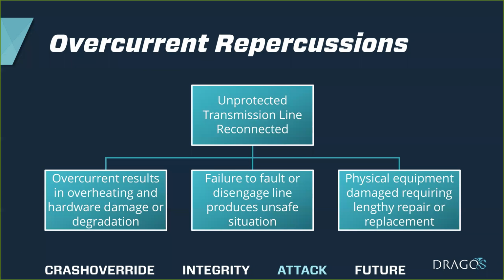And many of these conditions can combine to produce a scenario where, instead of it just being a matter of reclosing a lot of open breakers, you now have to actually repair or most likely physically replace damaged gear, which takes an outage that was originally a couple of hours into something that could last a couple of weeks or maybe even a couple of months, depending upon what equipment is damaged and to what extent.